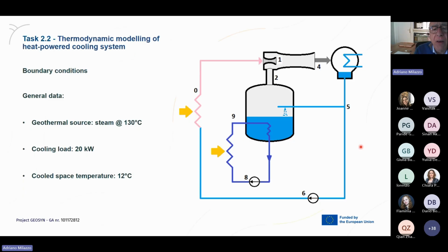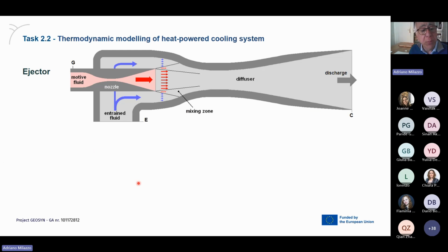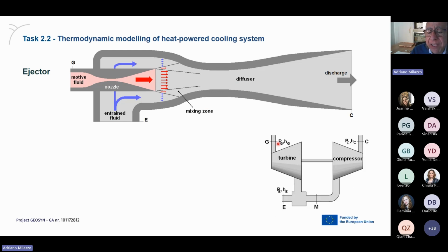For cooling, we were thinking of an ejector. These are the boundary conditions. Let's think of having steam entering at 130, which is the geothermal source. Let's say we have 20 kilowatts of cooling power, and we want to keep, for example, the room in which cheese is stored at 12 degrees. An ejector is a very simple device in which a fast flow entrains and compresses a slow fluid. So basically it's like having a turbine which gets a high pressure fluid and uses it to power a compressor that gets a low pressure fluid, and they both exit mixed on the discharge side.